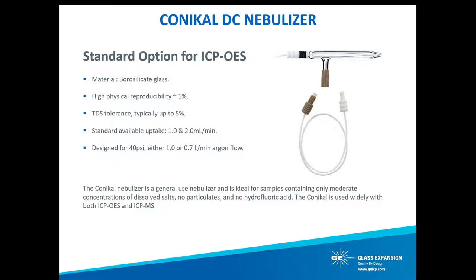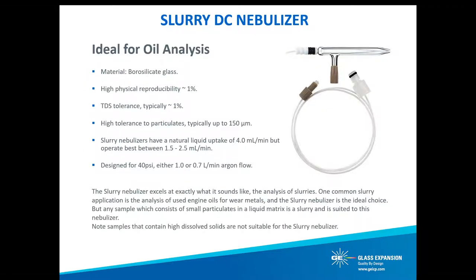We also offer a low uptake Sea Spray model for higher matrix ICP-MS applications where the MicroMist might suffer from salting. The Conikal nebulizer is Glass Expansion's high-performance general use nebulizer and is ideal for samples containing only a moderate concentration of dissolved salts. A number of instrument manufacturers employ this nebulizer as part of their basic instrument configuration. It is also a great option for the analysis of clean oil samples without any particulates. The Slurry nebulizer excels at the analysis of slurries — one common application is the analysis of used engine oils for wear metals.